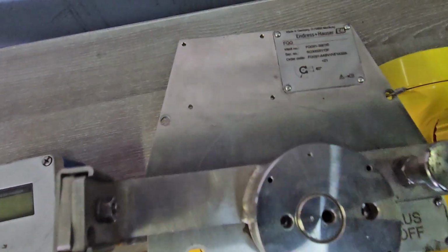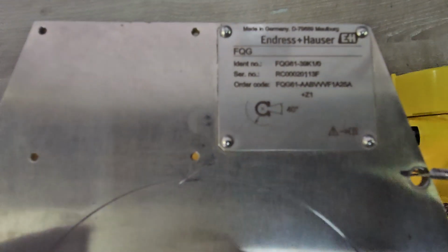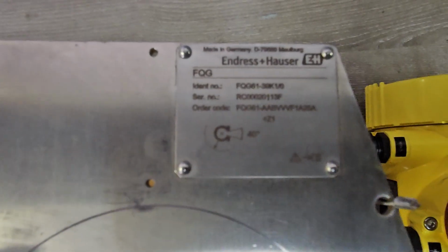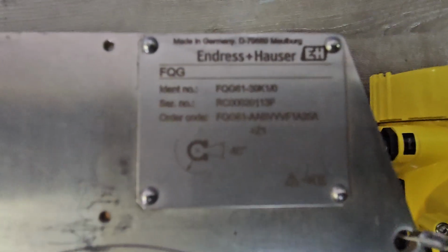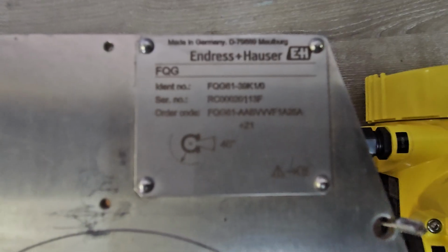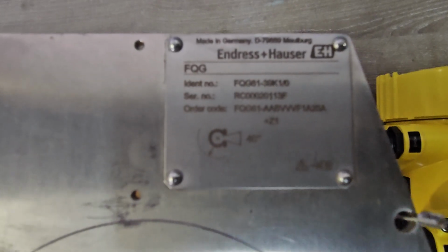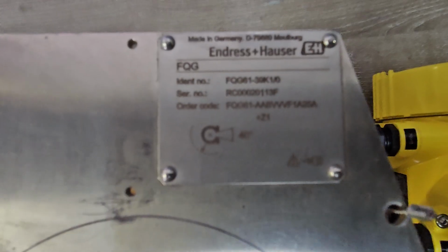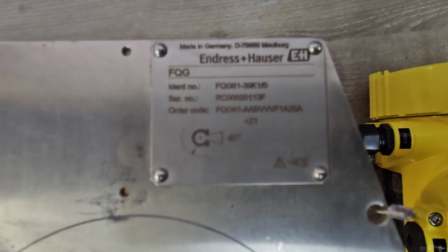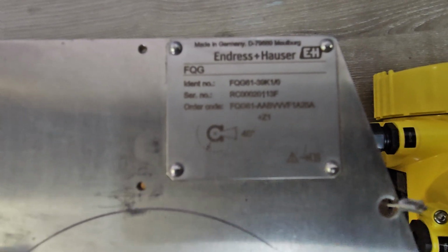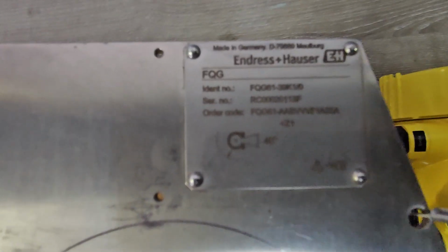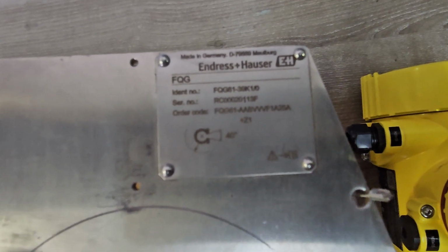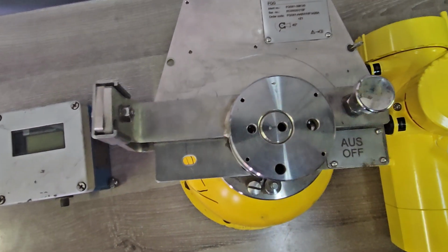But on top of here, it's manufactured for Endress+Hauser. And when the source contains something, there will be stamped on that nameplate the amount and the type of the radioactive component, which is cesium-137 or another type, and also the strength of the source, how strong that radiation source is. So that's how it works.